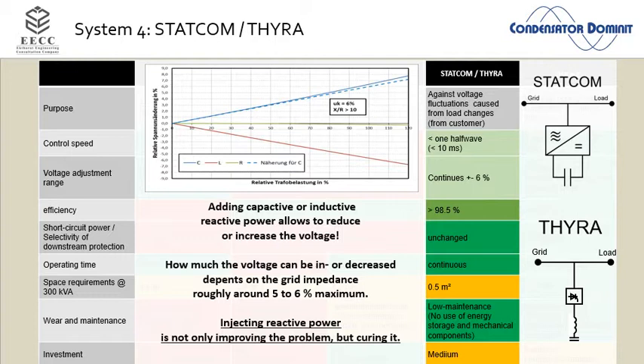Now when that stops under full load, so, sorry gentlemen, excuse me lady, excuse my French, then the shit hits the fan. To restart the conveyor belt, all those motors, it's hundreds of DC drives, try to start. The voltage goes down. But it's purely reactive power. A motor that doesn't move cannot consume active power. A motor that doesn't move is just a big inductor. So it's purely megavars. And then I can push in reactive power, I raise the voltage, and I cure the problem. I don't only fight the problem, I really cure it. Perfect. But it only applies if I'm producing the voltage sag by myself due to my motor start or my welding machine.